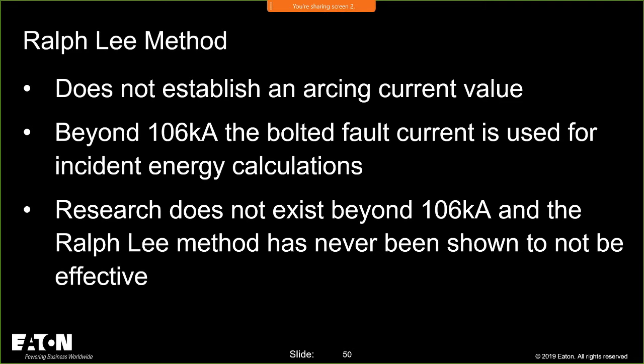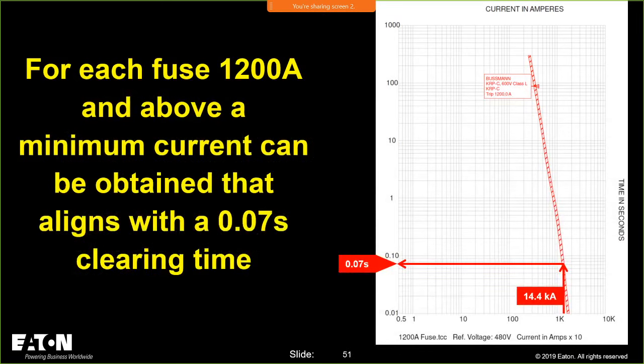So, if you calculated incident energy on these fuses and said, look, it's less than a calorie, go away, leave me alone, you could probably get an AHJ to accept that. But I'm an engineer, and I know a little bit more about these trip curves. I know that in some cases the arcing current is not going to be clearing as fast as what Ralph Lee's method says it will. But in any case, that's just me talking.